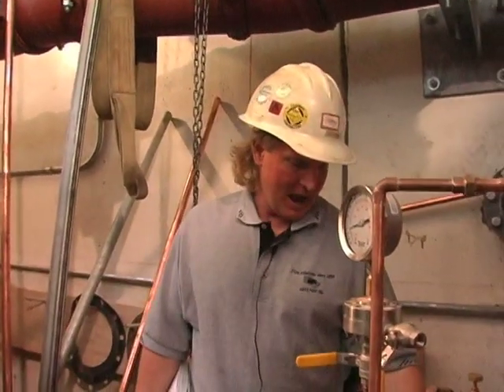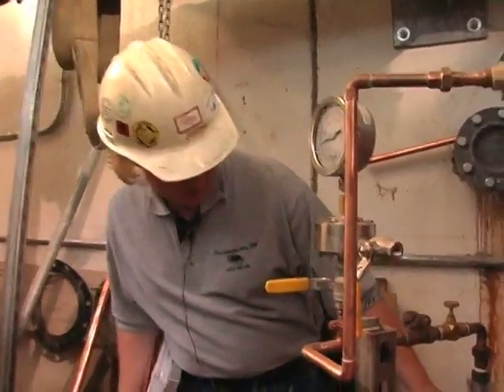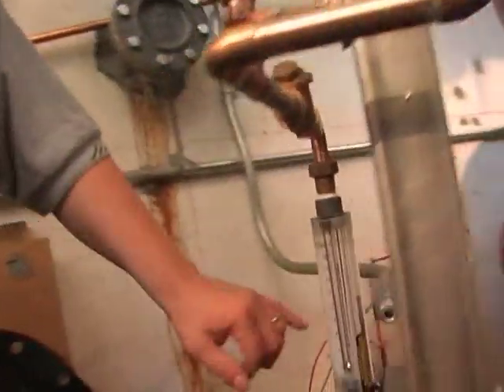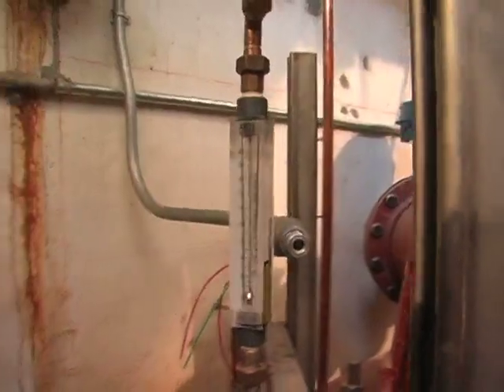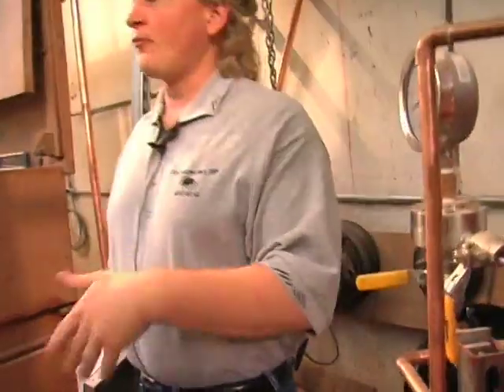You're just wasting water. Again, I don't know if it just recycles itself again and again. If it is, it's not going to hurt it. But again, between 1 and 1.5 gallons a minute. 1 gallon a minute right there. That's all you're going to want. Make sure it stays around 1 gallon a minute. And again, it's the same as all the seals. That should be more than enough water to lubricate it, keep everything wet and good.